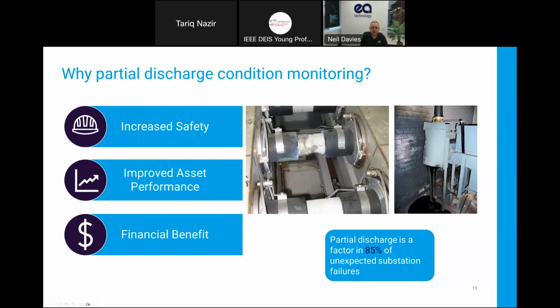Many years ago, we looked at a set of statistics, more from the UK than anywhere, where we determined that the root cause of unexpected substation failures, so the blowout, if you like, such as we see in the compound insulated cable box that's gone on the picture here, was 85% of those failures were generally associated with insulation breakdown, on which partial discharge is going to be a factor. So that's really why companies will carry out this testing.